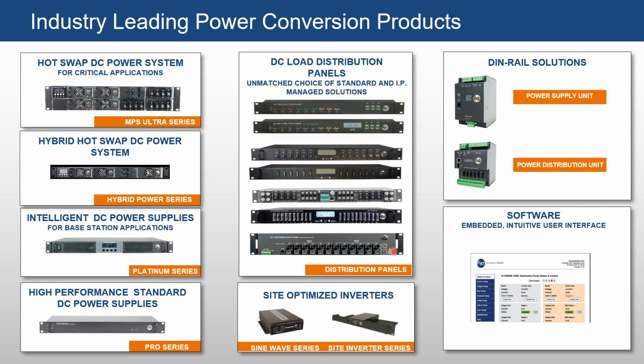We didn't touch much on this. This is in particular for 5G applications. This variant is for minus 48 volts, and it can provide remote monitoring and control up to a 63 ampere rated breaker, that's 50 ampere continuous, dual feed, 12 outputs.